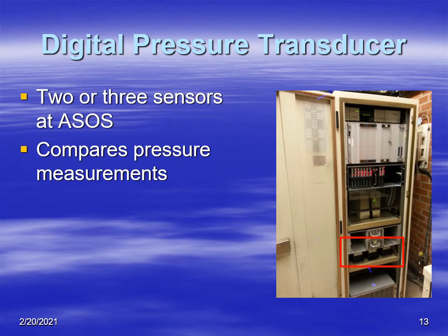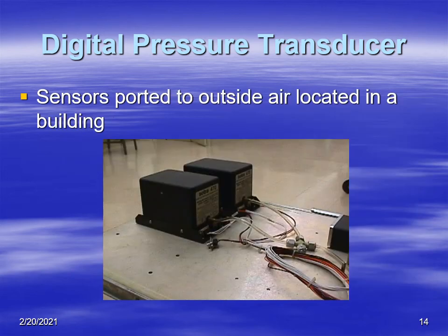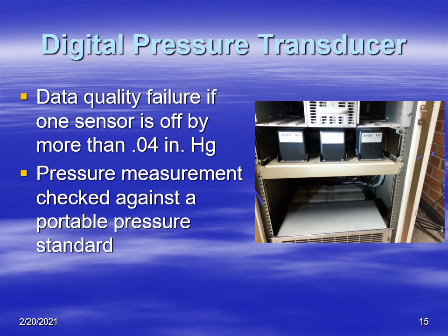With an ASOS, there are 3 pressure transducers located on the inside of a rack inside a building. They don't put these pressure transducers outside in the elements. They keep them inside. There are static lines that go to the outside of the building so that you can measure true atmospheric pressure. The reason you have 3 sensors is that if one starts to drift and go out of calibration, the other 2 should have the accurate measurement, so you can tell which instrument is bad.